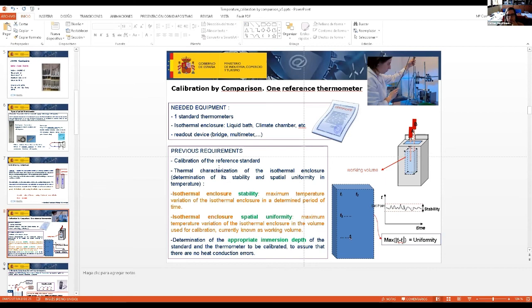But previously, to start the calibration of our thermometer, we need to check several things. First, the reference standard needs to be calibrated. Second, our isothermal enclosure needs to be characterized. What does it mean? It means that we have to know its stability and its spatial uniformity. Just to keep our experiment under control, just to be sure that the thermometer under calibration is at the same temperature as the standard. And also, due to the working principle of the thermometers, we need to determine the appropriate immersion depth of the sensor in the isothermal enclosure.